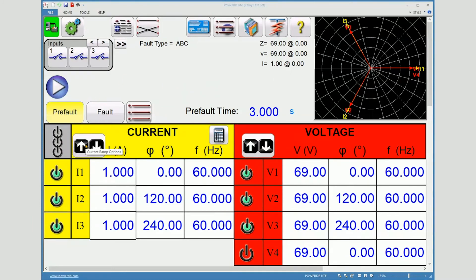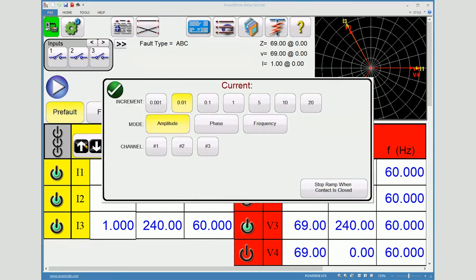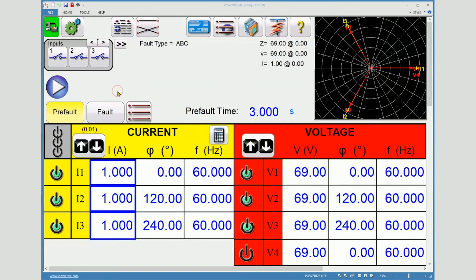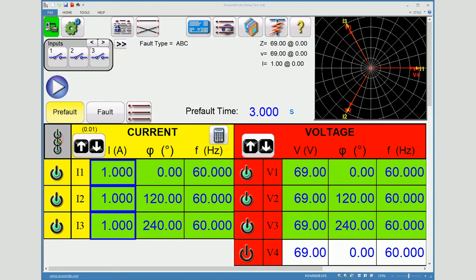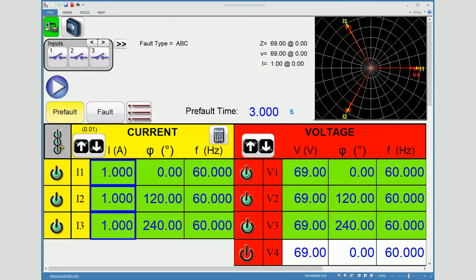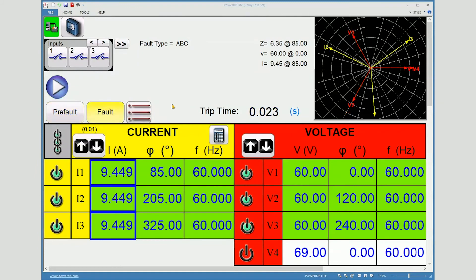And I need to configure my ramp. Set three-phase ramp. Accept the change. Hit the master on button. Switch to fault. I can now begin using my wheel mouse to ramp. Notice the contact actuation as I approach 6.24 ohms.